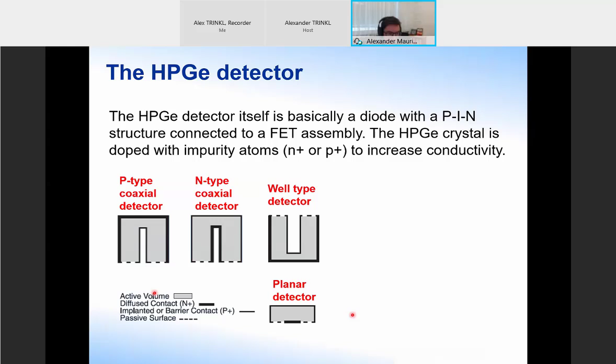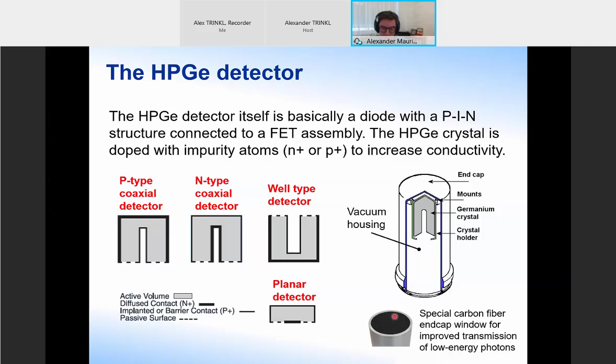Then what you'll have is that you'll mount your crystal into a vacuum housing with a holder, and there'll be vacuum in here to keep the crystal completely isolated from the environment, also for thermal conductivity to reduce that. And then you have this end cap around to protect the detector. So when you are looking at the detector from outside, you never actually see the crystal. You see the end cap. That's usually like an aluminum cylinder looking thing. Though nowadays you see more and more where the top of the detector, where you might place your sample, is replaced, and instead of aluminum it might be something like carbon fiber. Carbon fiber, having a lower atomic number and lower density than aluminium, has better transmission for low energies of gamma rays to reach into our detector.